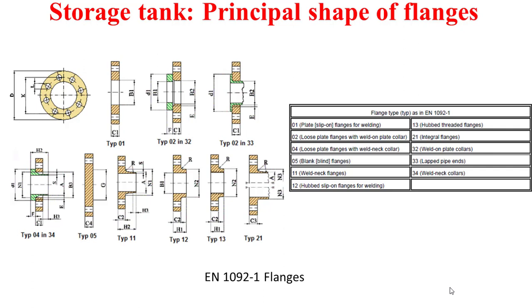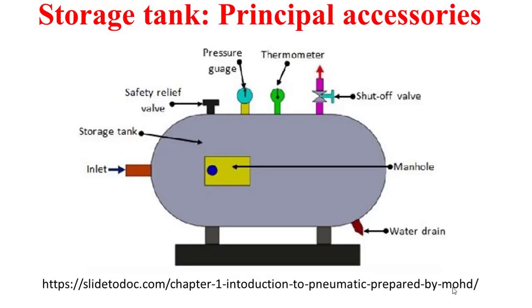For the flanges, there are some principal types, as you can see in this slide. These types are extracted from the European standard EN 1092-1. For example, type 01 is called plate flanges for welding, and type 04 and 34 are called loose plate flanges with weld neck collar.